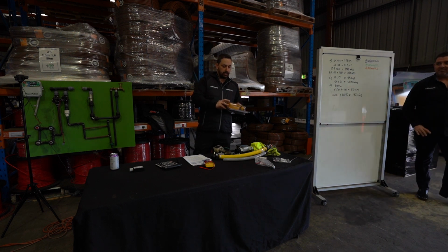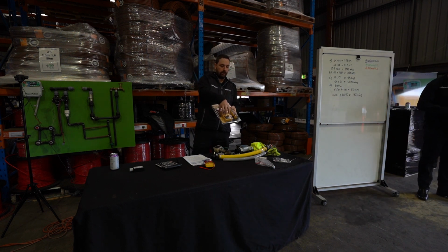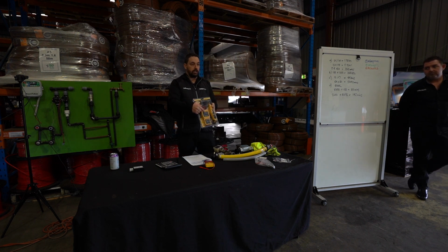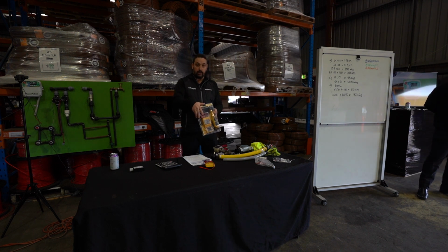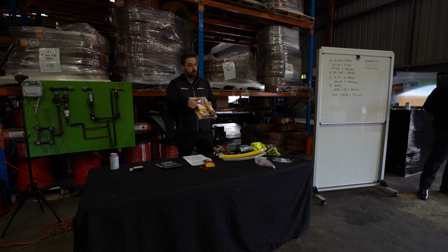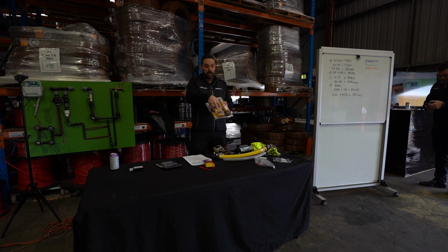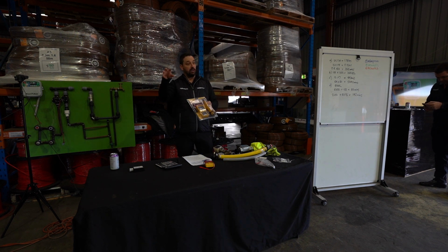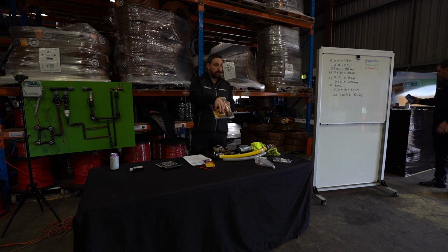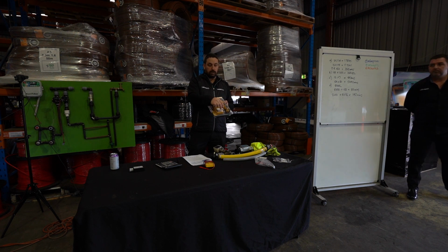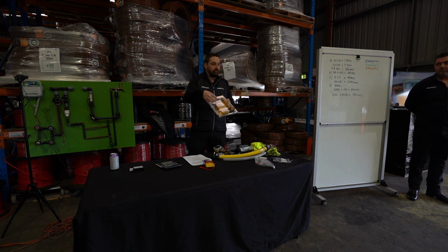These are pretty similar things. You can buy this as its own unit, or you can buy this as it is now with a kit. Same sort of thing. We can test control wires with the unit, and it will tell whether we've got a good circuit or a short circuit. We can also send signals down the line with this unit and activate. If you don't have a power source available, this can also turn on coils for us, with the batteries packed inside. Obviously it won't last forever, but it's going to be able to let us turn things on.